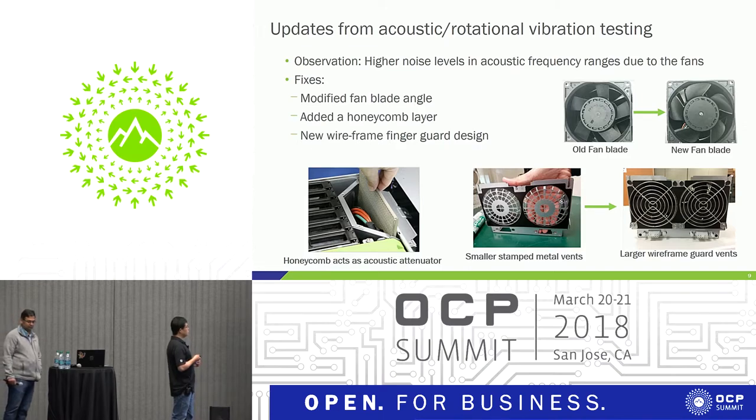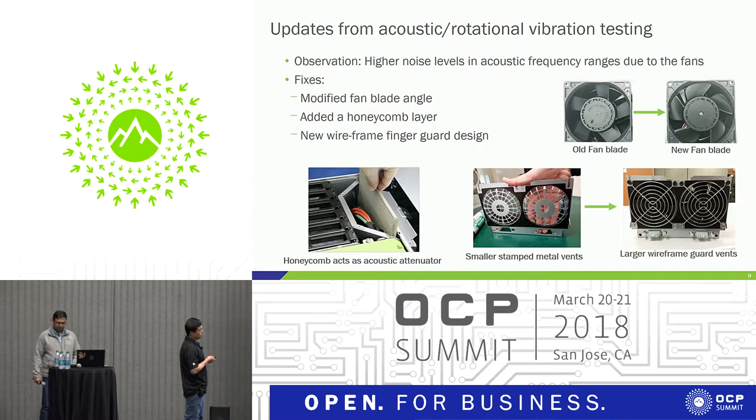We resolved the issue from multiple angles. The first is fan blade shape — the shape of a fan blade, especially the edge, has a great impact on noise generation. We changed the edge from a straight edge to a curved edge with a smoother tip, which generates much less noise and improves hard drive performance significantly. Since there's no way to totally avoid the noise, we can attenuate it: we designed a honeycomb-like attenuator placed between the hard drive and the fans, sized to absorb most of the noise. The last change is the finger guard design — we reduced the area of the finger guide by changing from smaller stamped metal vents to a larger wireframe guard vents.